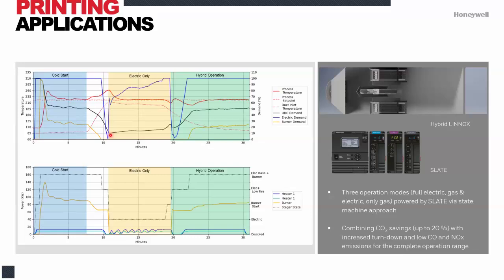For the customer, we did this operation: we simulated the system up and running, then going into recirculation mode. Demand is dropping, preheat temperature here in the dashed red line is increasing. The system automatically recognizes it doesn't need this much heat anymore and switches to an all-electric state, maintaining all-electric. You see down here the capacity of the burner drops to 0, and the blue and teal lines are the capacity of the heaters, fluctuating slightly to maintain the heat load.